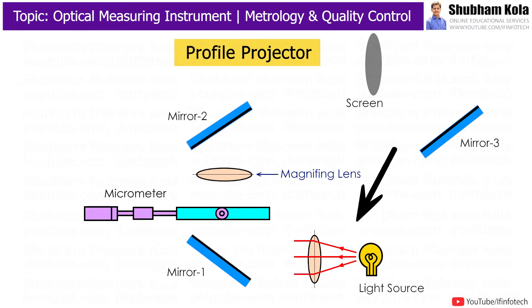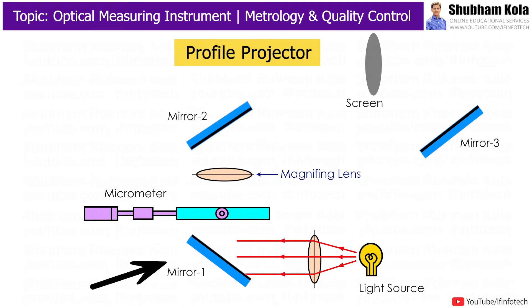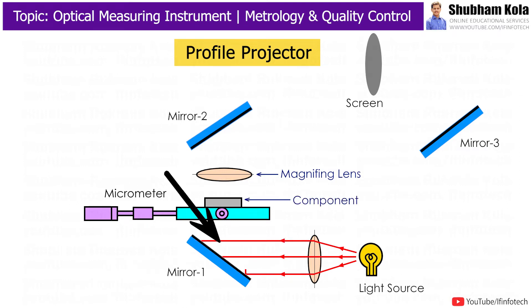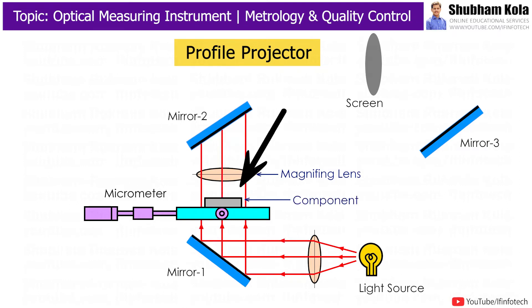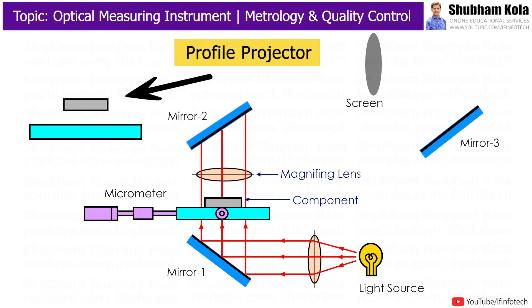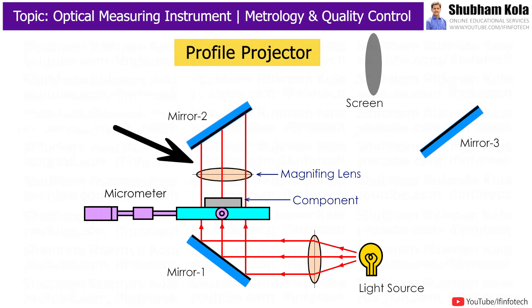The light source incidents light on a mirror to create the profile of the component. The table is made up of glass on which the component can be mounted. Magnifying lenses are used to magnify the image of the component, and the magnification of up to 10x to 500x is possible.